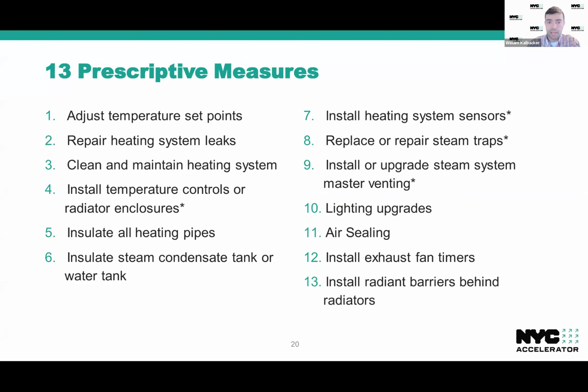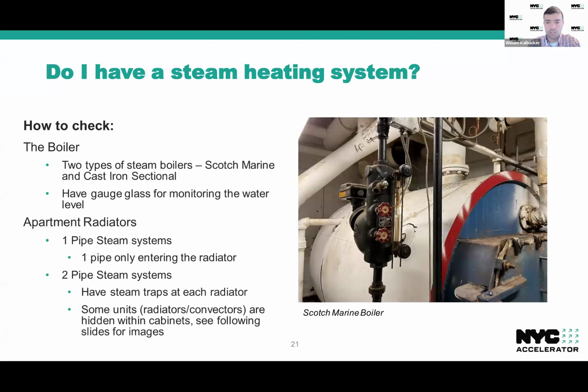But with that, let's talk about steam first, because a couple of these measures are really appropriate for buildings that have steam heating systems, and just knowing if your building has a steam heating system is really important. So how do you check if you have a steam heating system? Very basically, there's a couple ways to make sure that you do have steam. By looking at the big thing in the basement, the boiler, there are a couple different types that produce steam. Typically, you might see a Scotch marine boiler, which is a big cylinder type shape. And we also have sectional boilers, which are more rectangular, both capable of producing steam. But another giveaway is that you might see a sight glass located there with a water level indicating how much of the boiler is filled up with water. That's a pretty dead giveaway that you have a steam system.